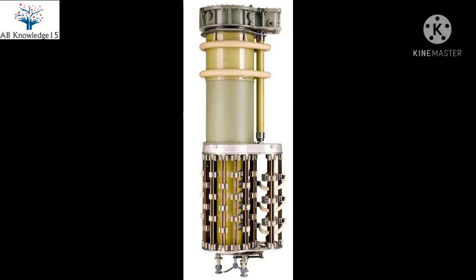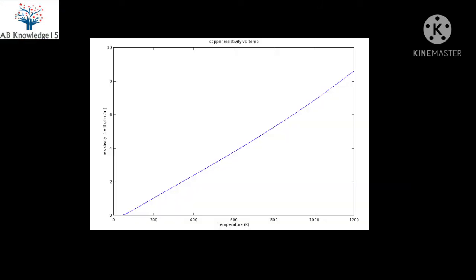For on-load or off-load tap changer transformers, the test is done for each tap to cover the full winding of the transformer. We can keep the test kit on while changing the tap in the on-load tap changer transformer, but we should keep the test kit in off condition while changing the tap in the off-load tap changer transformer, so as to prevent any sparking inside the transformer.